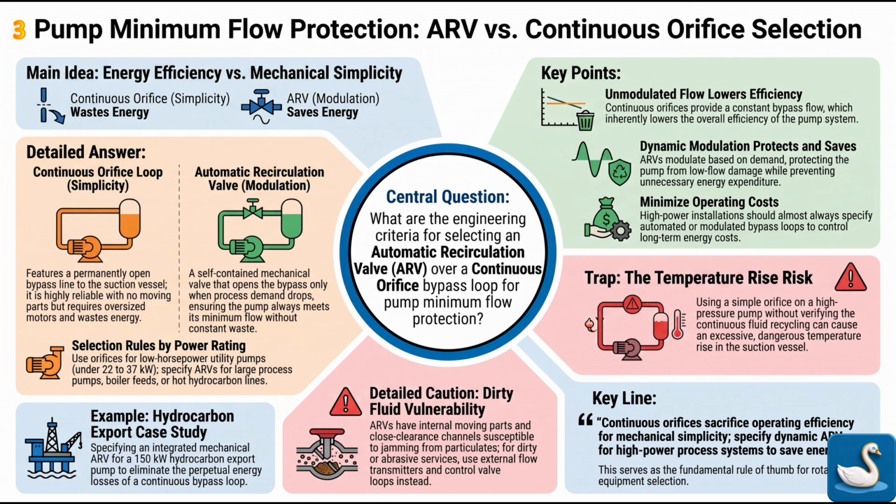Exactly. Over time, this continuous fluid recycling will cause an excessive, dangerous temperature rise inside the suction vessel. It will eventually heat the fluid beyond its vapor pressure, vaporizing the liquid in the vessel and causing a total catastrophic loss of suction to the pump. So it destroys the pump anyway. Yes. Continuous orifices sacrifice operating efficiency for mechanical simplicity. You must specify dynamic ARVs for high-power process systems to save energy and prevent thermal leaks.